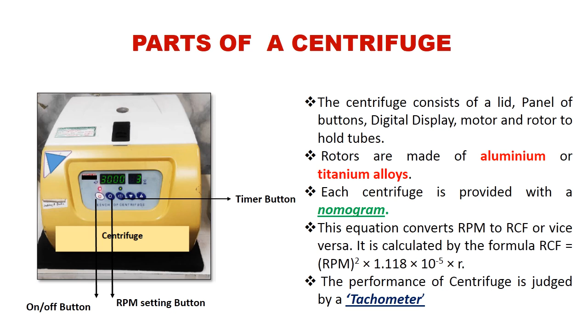According to the maximum RPM, centrifuges can be classified into three types. Low speed or benchtop centrifuges can attain a maximum RPM of 4,000 to 6,000. High speed centrifuges can attain a maximum speed within the range of 15,000 to 25,000 RPM, and the ultra-centrifuges 70,000 to 80,000 RPM. They are mainly designed for extraction of cellular organelles, and they are also known as refrigerated centrifuges or commonly termed cooling centrifuges, because a huge amount of heat will be generated at this speed. So a cooling chamber is provided with this type of centrifuge. That's why they are also known as refrigerated centrifuges.